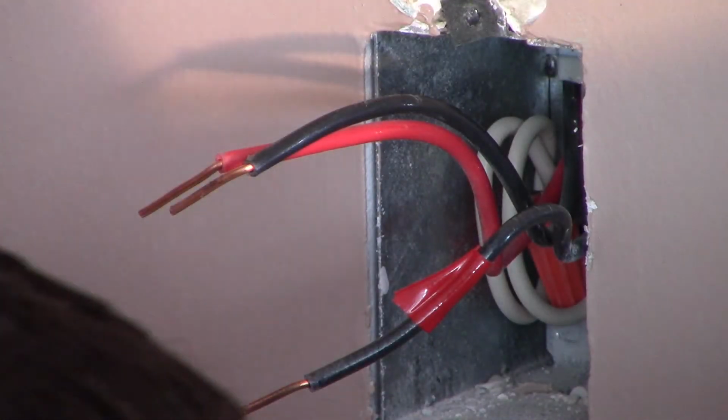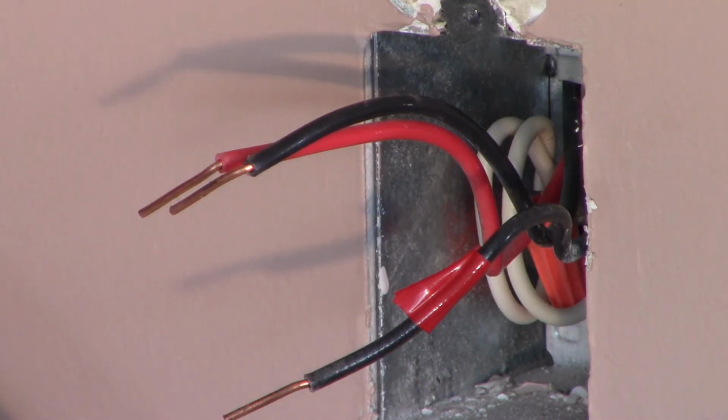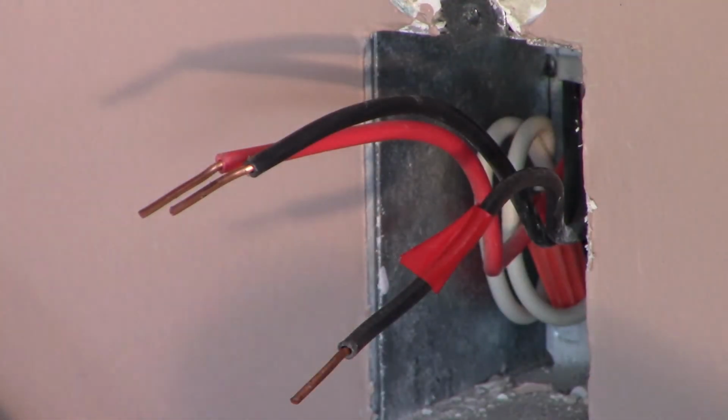I don't like these push-in connections. The reason is because they're a little tricky to get out when the switch gets old and you take it out later. They get brittle with age, and that's kind of a minor thing. The most important thing about not using those is it's just a little spring tab pushing against the wire, and in my opinion, it doesn't make good enough contact to be reliable. I would say a good wrapped conductor, wrapped around the screw, is the most reliable connection.